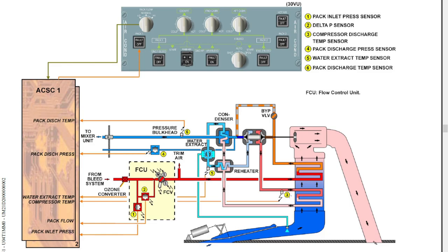So now there are three states when it comes to the compressor discharge temperature sensor. So we'll say now the air coming from the compressor is at 170 degrees to 180 degrees. Okay, if the temperature of the air coming from the compressor is less than or equal to 180 degrees, the system will operate in normal condition.